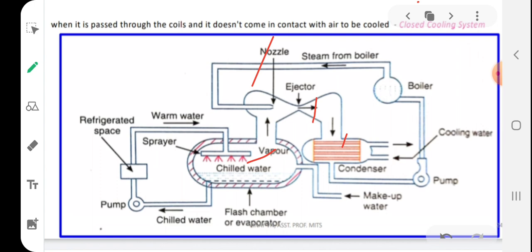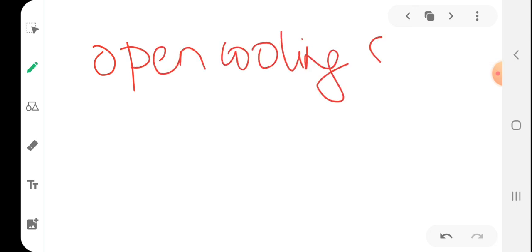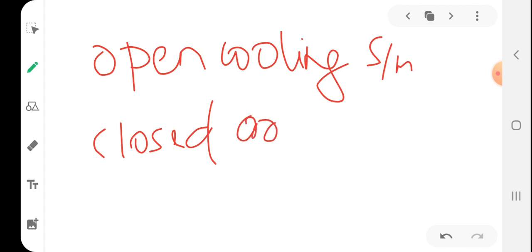So you can see here the chilled water. I will explain the working, but before that, just to give an idea: we are reducing the pressure of the water so that we can boil the refrigerant, the water, at a lower pressure. So how is this reduced pressure maintained at the surface of water? By throttling the steam through jets or nozzles. Students, when chilled water from the flash chamber is directly used in the form of spray for cooling air, it is called an open cooling system. So there are basically two types of system: open cooling system and closed cooling system.